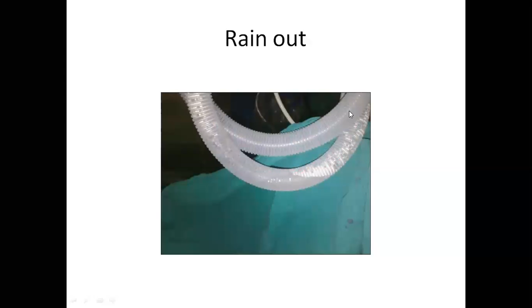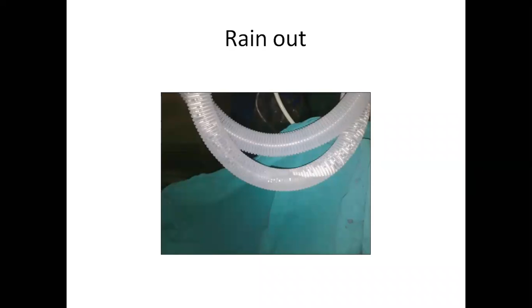Thankfully we have the technology to have humidified gas, but this is called rain out. And so we have hot humidified gas coming off the humidifier hitting a cold circuit. It's not the same temperature. And so that cold gas causes that water to condense. So the patient doesn't get as much as they could have, and a lot of that humidity rains out. So we have to keep these lines clear of water, and so it's a lot of work for RTs.